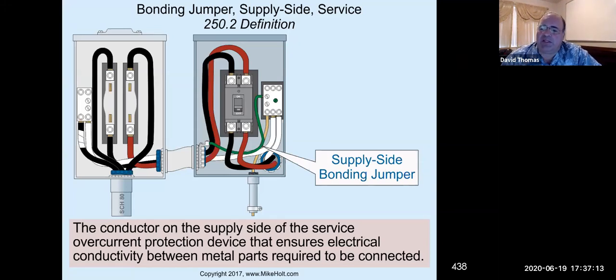The bonding jumper, this is on the supply side. This is the jumper that ties, in essence, the meter, that's your meter outside your house. Typically, this stuff will be in one enclosure, so this picture doesn't really apply. But if we did have two separate enclosures, we have to make sure that we bond the actual conduit between the main breaker and the stuff that's coming from the utility.